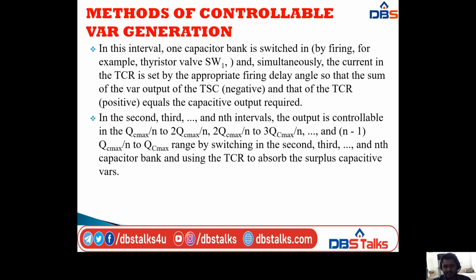Next, in the first interval, one capacitor bank is switched in. That means by firing, for example, thyristor valve switch 1, only switch 1 and the corresponding capacitor are working. Simultaneously, the current in the TCR, that is ILF of alpha, is set by the appropriate firing delay angle alpha, so that the sum of the VAR output of the TSC, which is generally negative, and that of the TCR, which is positive, equals the capacitor output required for that interval.